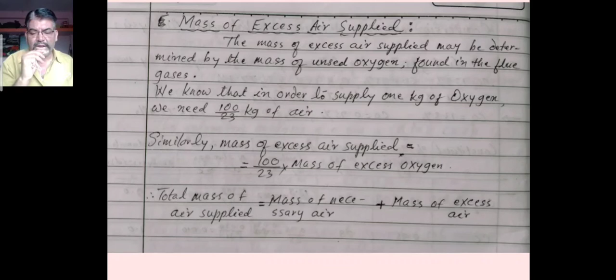Now the next heading which is given is mass of excess air required. The excess air supplied may be determined by the mass of unused oxygen found in the flue gases. Therefore the formula for mass of excess air supplied is equal to 100 divided by 23 into mass of excess oxygen, and the total mass of air supplied is the mass of necessary air plus the mass of the excess air.